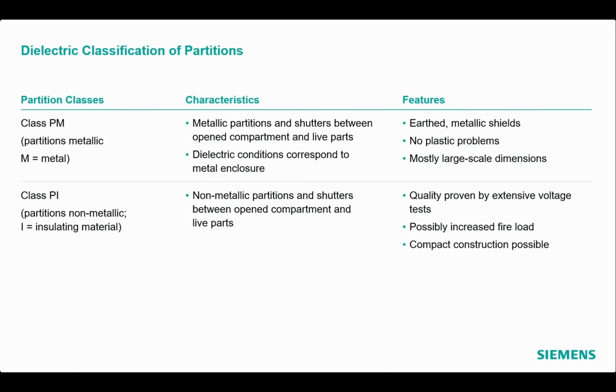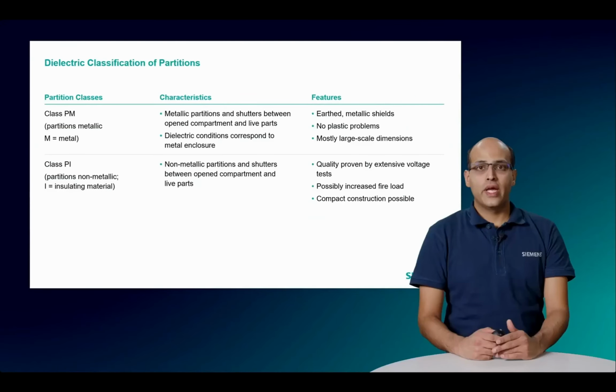The PI class is characterized by the use of non-metallic partitions and shutters made of insulating materials between opened compartments and live parts. The quality of such insulating materials needs to be proved by extensive voltage test. Although construction is possible with compact design, this could lead to fire load because of isolating materials used. While both classes are designed to enhance safety, the PM class offers a higher level of protection compared to the PI class. However, the choice between them is based on the specific requirements of the installation.